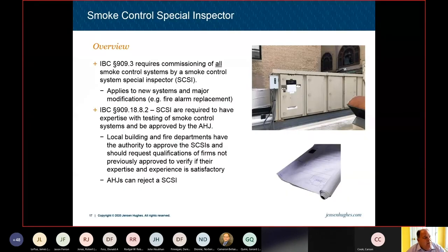That person's looking to tie up all those loose ends and how it all fits together. So now, once again, for any new smoke control system or major modifications to smoke control systems, sometimes that includes fire alarm system replacements, whether you're upgrading the panels or doing a full replacement of the fire alarm system. If that fire alarm system is also controlling smoke control, there are things you need to watch out for. But we're going to talk more like it's a brand new building, brand new job.